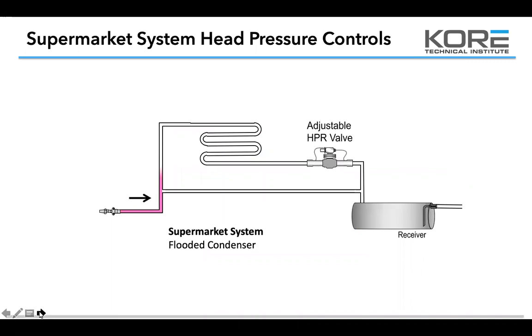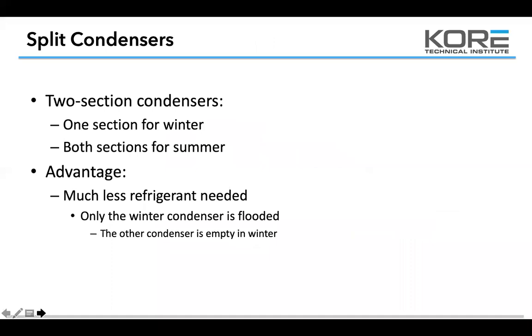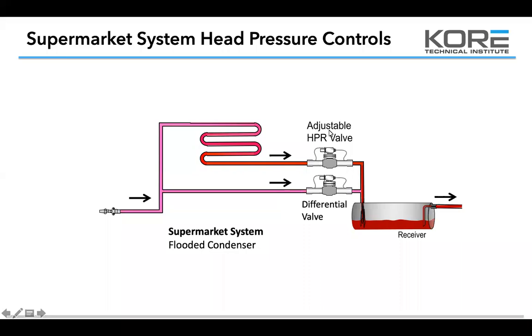Supermarket head pressure control is the same concept. On smaller racks you see the headmaster; on larger rack systems you have an adjustable head pressure control and a differential valve, both adjustable. The concept is the same — we're trying to stack liquid in the condenser to eliminate the condensing surface so we can keep that head pressure at a certain level, so as it pushes down through the liquid line we get enough differential across the valve to feed a good nice feeding pattern in that evaporator through the metering device.